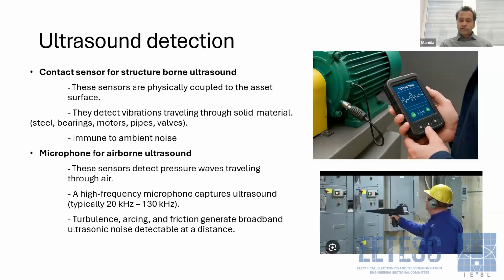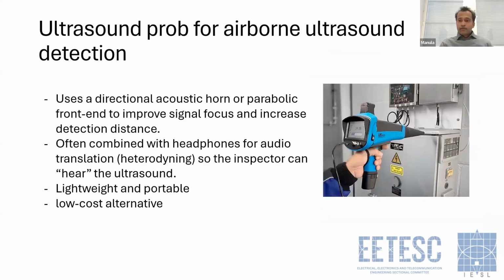If you take, for example, medium voltage switchgear, you can't put your contact sensor on each compartment. On one hand it is not safe, on the other hand it is not practical. So in that case, we can use airborne ultrasound to detect, for example, partial discharges. We can do this kind of inspection at a safe distance with airborne ultrasound. So this is an example case of using airborne ultrasound.